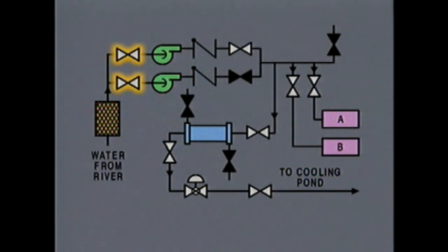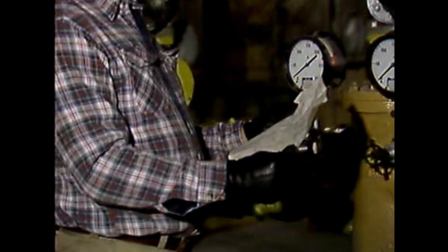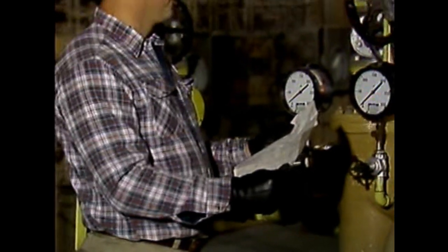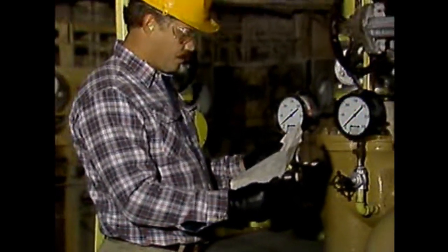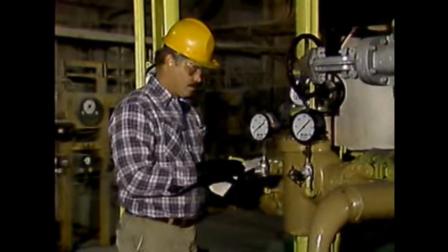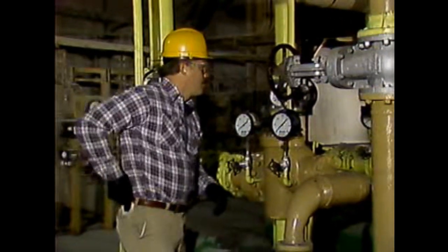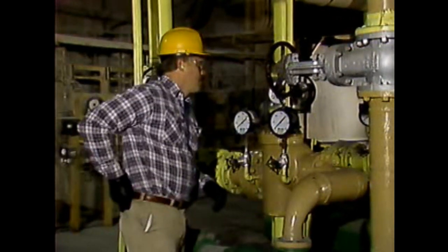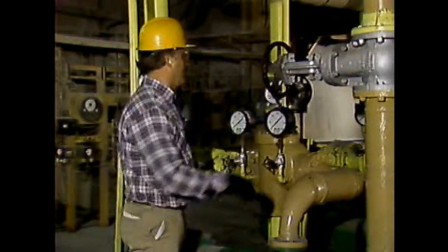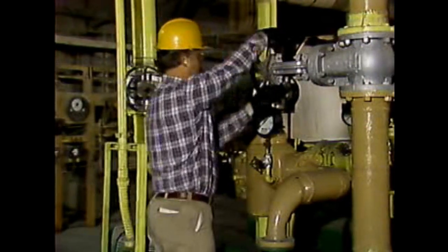These valves must be opened to allow water to enter the pump suction piping. When this system is started up, only one of the pumps will be placed in service — the second pump will be on standby. However, the suction valves for both pumps are opened so that the second pump can be started quickly if it's needed.